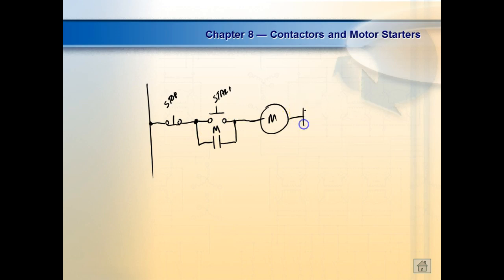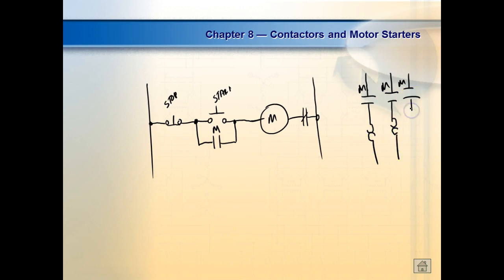And then this is where the overload contact would be. So our power circuit might look like this. I'm not going to draw all the disconnects and the fuses. So we'll just start off L1, L2, L3. Then we'd come through our contacts. These are your main contacts on your motor starter. They're going to have the same name as these, but these are over in the power circuit, right? Understand? Then I'll drop down here and I'll have my overload sensors. This would be my motor. Okay. Everybody okay so far?